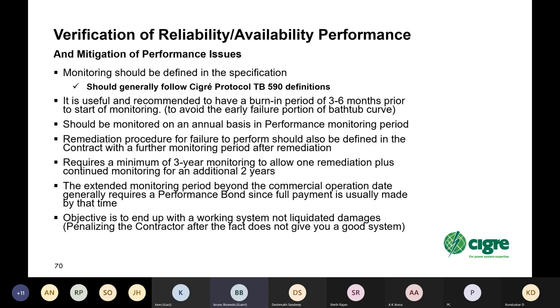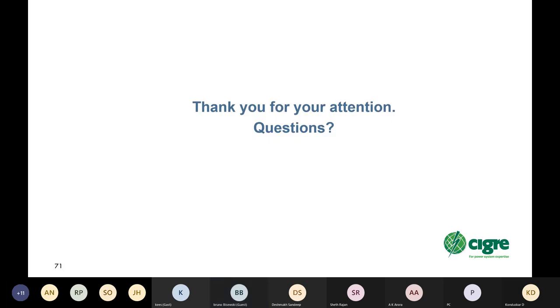Such an extended monitoring period beyond the commercial operation date generally requires a performance bond, since full payment is usually made by that time. So you have to hold a bond if you want to ensure that the supplier is going to be receptive to making further changes to achieve reliability targets. And finally, the objective is to end up with a working system, not liquidated damages. Penalizing the contractor after the fact doesn't give you a good system. So it's worthwhile having the remediation done rather than the liquidated damages. Right. With that, I'll finish and open it for questions. Thank you.